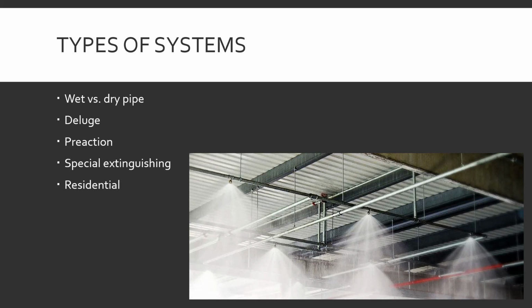Special note: if you go to a special extinguishing alarm, be on air, be on your air packs. With the water ones, you go in, and if there's water, you go, yeah, it's a false alarm, but there's water all over the floor. Now I'm wet. That sucks. Or you go in and there's nothing, and it's like, oh, there's a problem with the system. There's not actually any water flowing. No big deal. Figure out what the actual problem is.